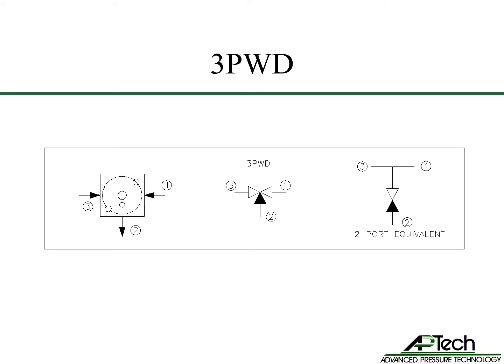The image in the center is a 3PWD schematic. Ports 1 and 3 are open triangles indicating inlet ports, and the solid triangle port 2 is the outlet port. The image on the right is a two-ported valve schematic equivalent of the 3PWD. There are two inlets, ports 1 and 3, which T into the valve inlet port — the empty triangle. The gas exits the valve through outlet port 2, the solid triangle. Ports 1 and 3 enter the valve below the seat, and port 2 exits the valve downstream of the seat.